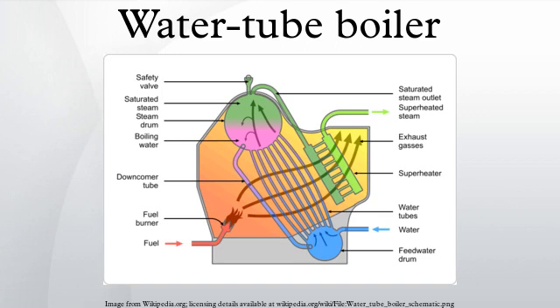Stationary: Modern boilers for power generation are almost entirely water tube designs, owing to their ability to operate at higher pressures. Where process steam is required for heating or as a chemical component, then there is still a small niche for fire tube boilers.